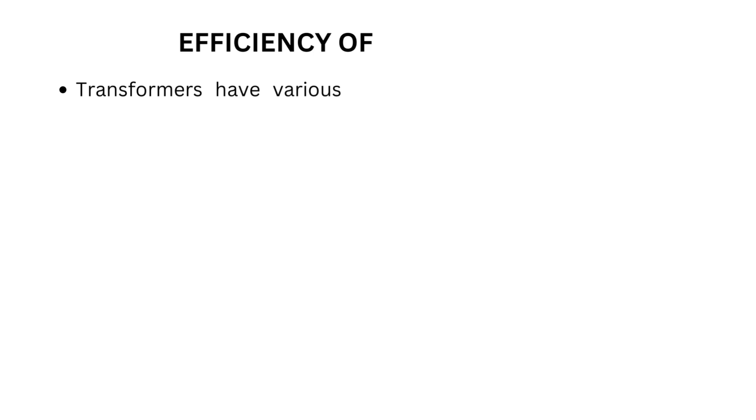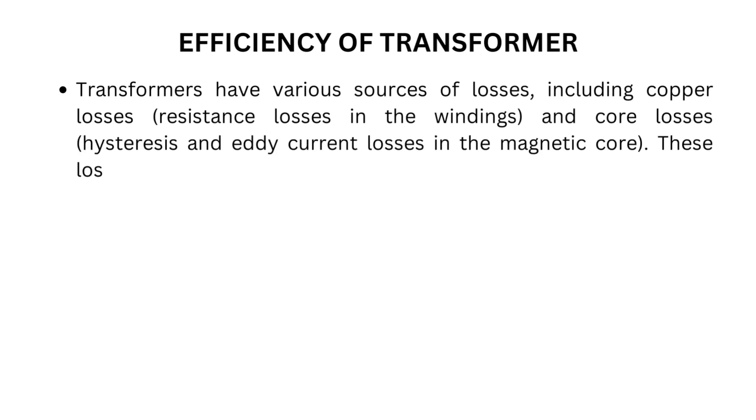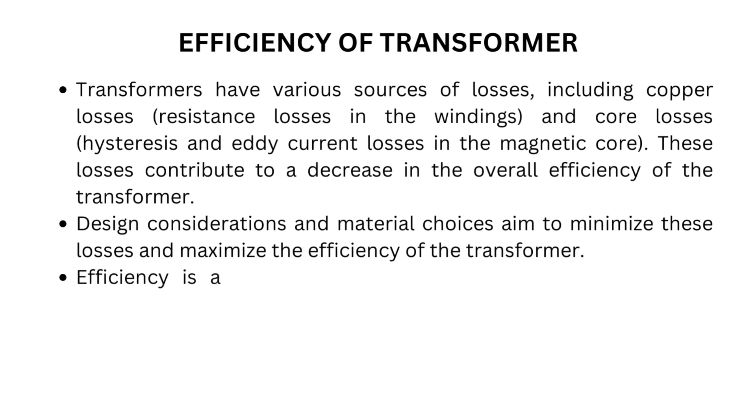Transformers have various sources of losses, including copper losses (resistance losses in the windings) and core losses (hysteresis and eddy current losses in the magnetic core). These losses contribute to a decrease in the overall efficiency of the transformer. Design considerations and material choices aim to minimize these losses and maximize the efficiency of the transformer.